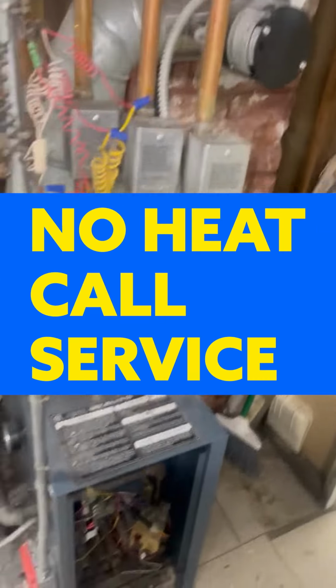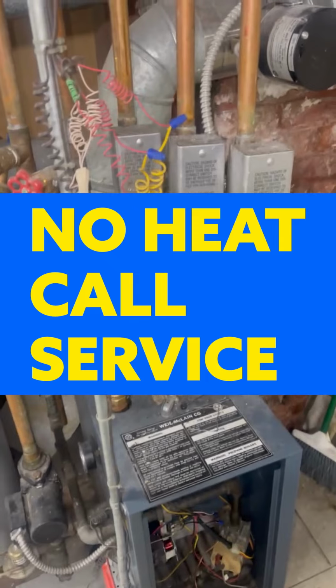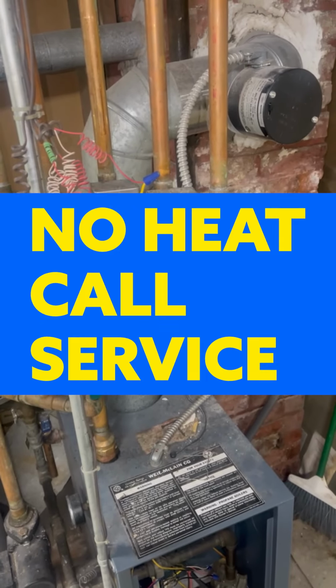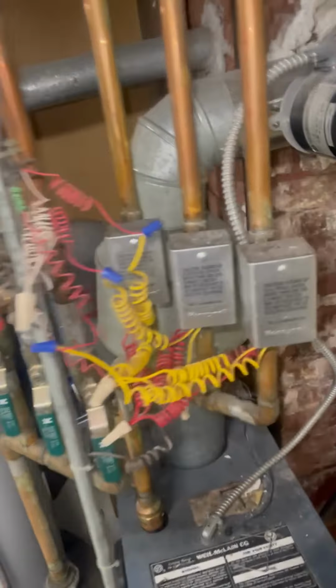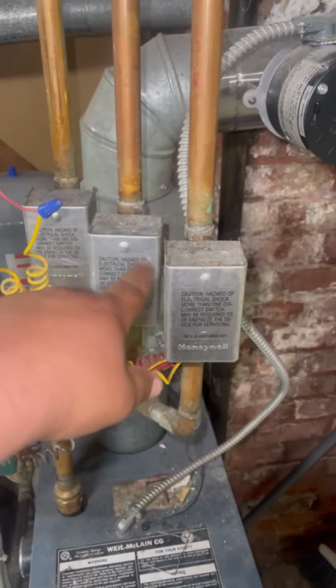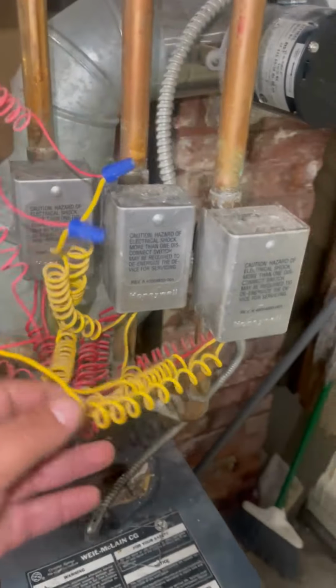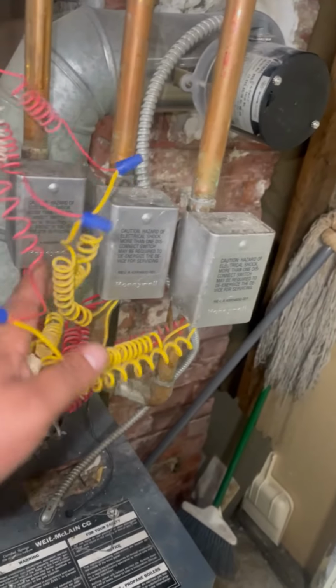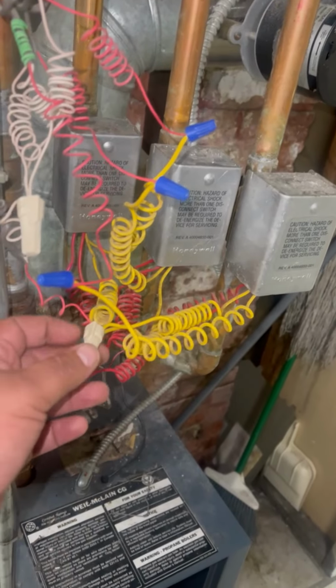Guys, we're getting the cold here in Boulder, New York for no heat, believe it or not. So it's been a little chilly here in New York in the evenings. So as you guys can see, these are zone valves. These are 3 zones and there's 4 wires. 2 of them are end switch and the other 2 are power, 24 volts.